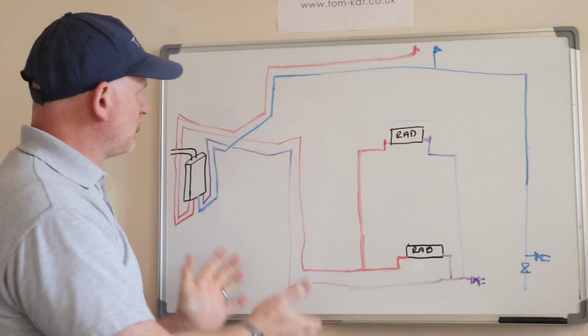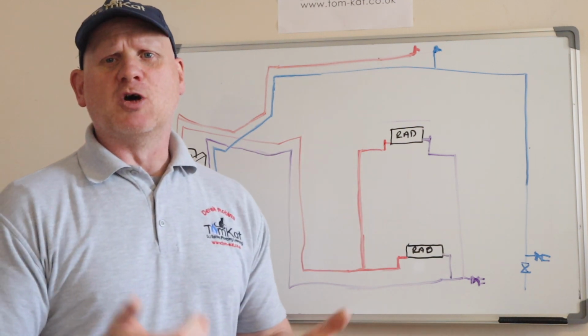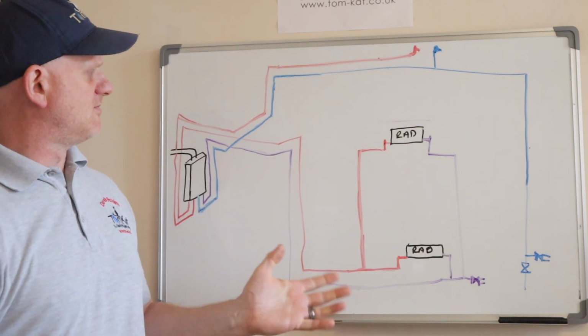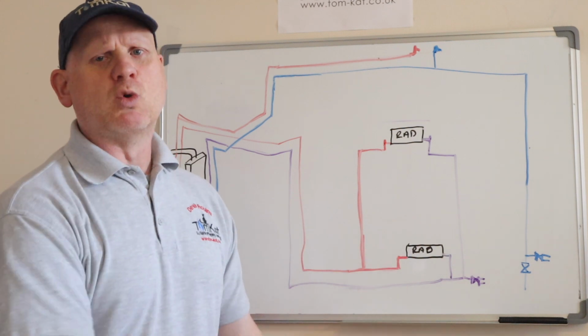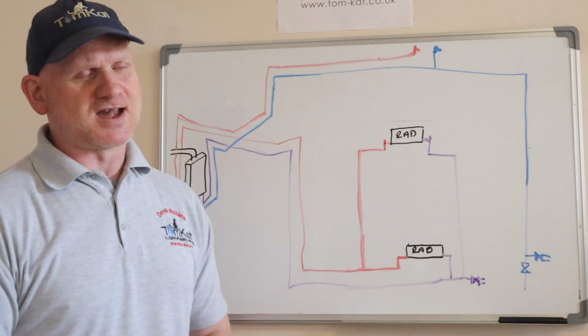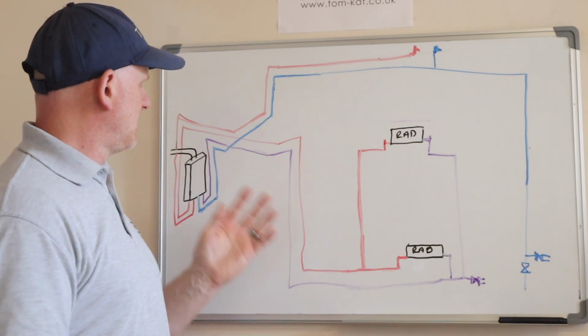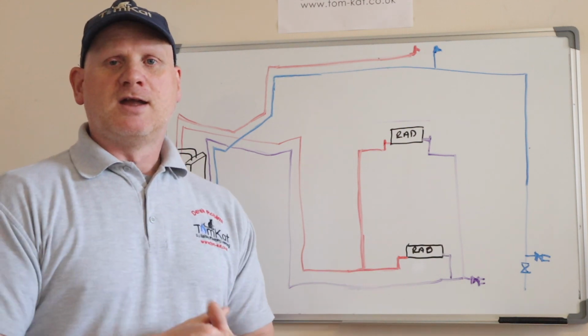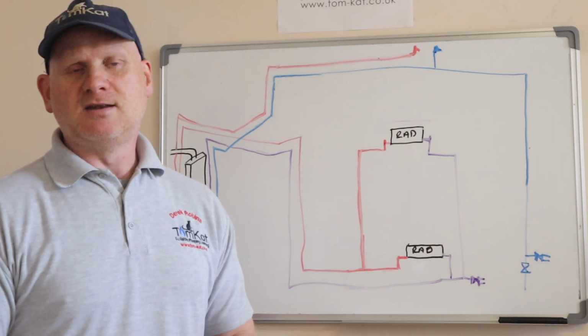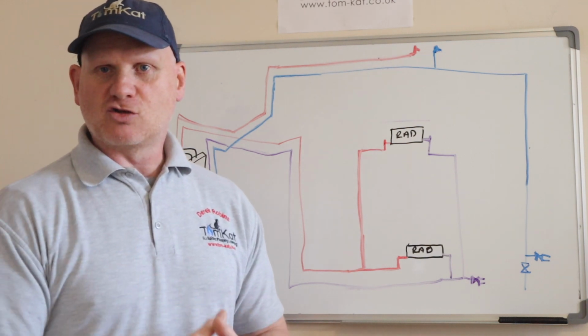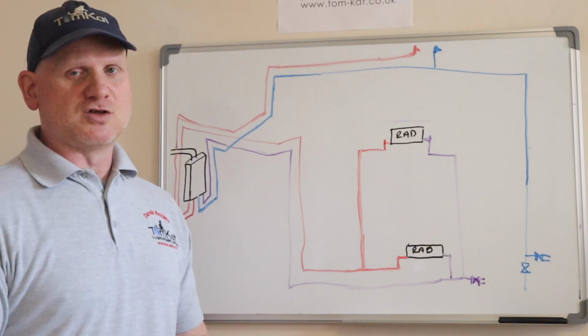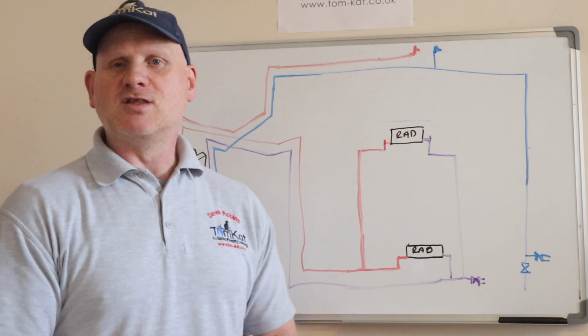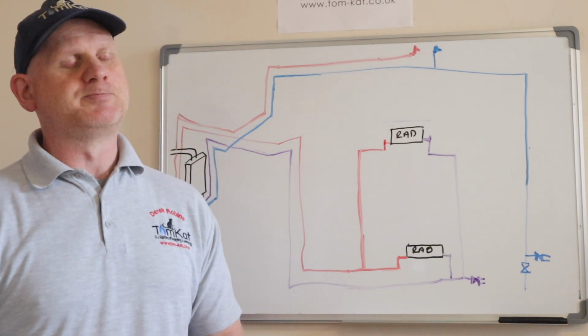So as you can see from the drawing and you can see from the film how easy it was for us to convert it, you're basically doing away completely with the gravity side and you're just connecting the flow and return off the boiler into the heating, making sure you're going into the 22mm flow pipe and the 22 return, and then connecting anywhere into the hot and cold water system.